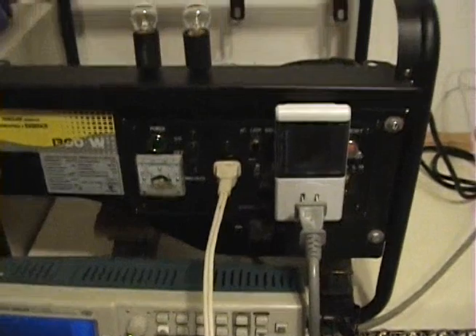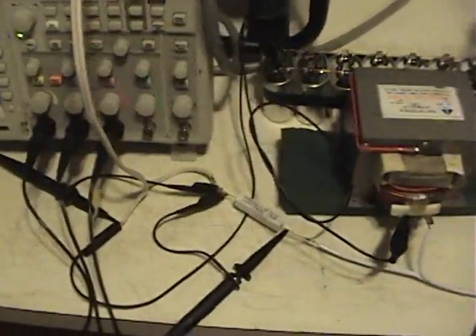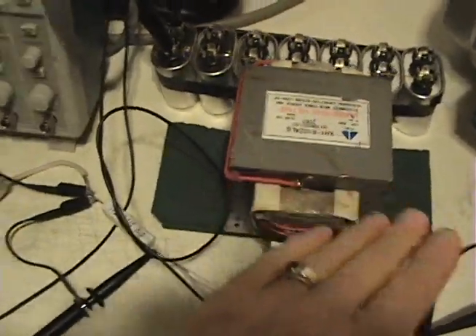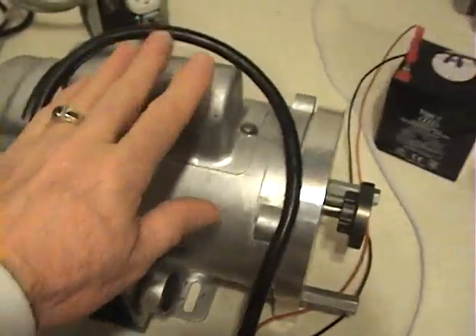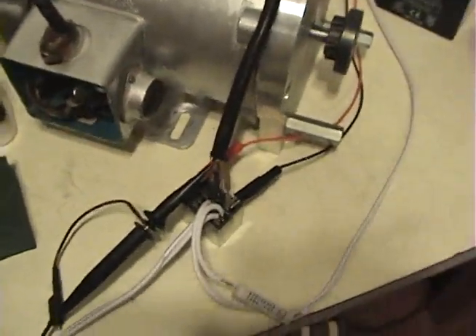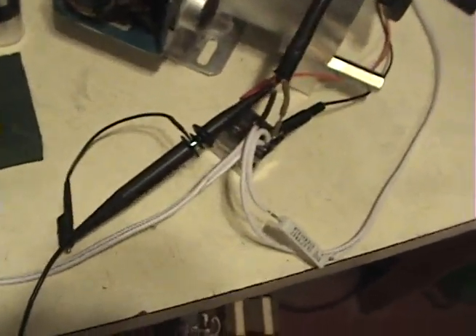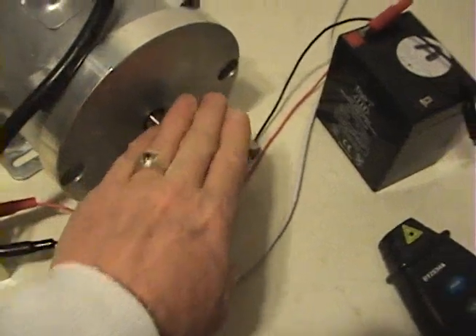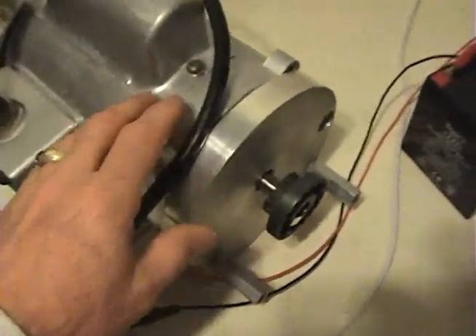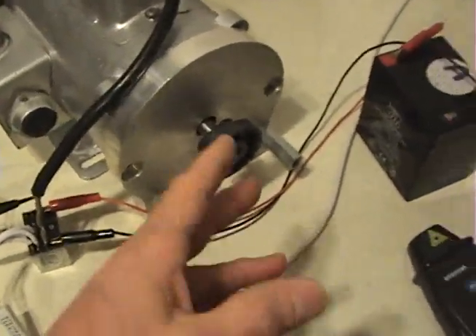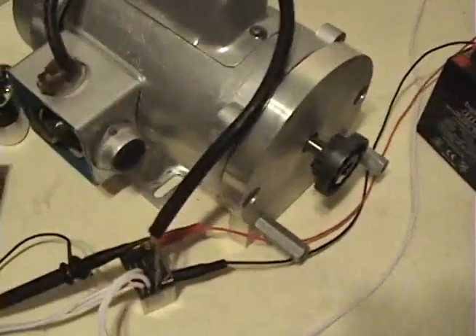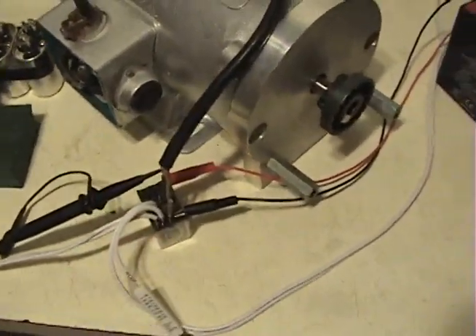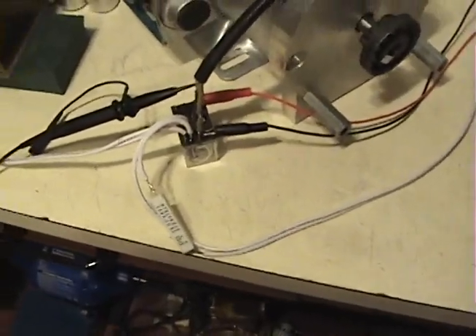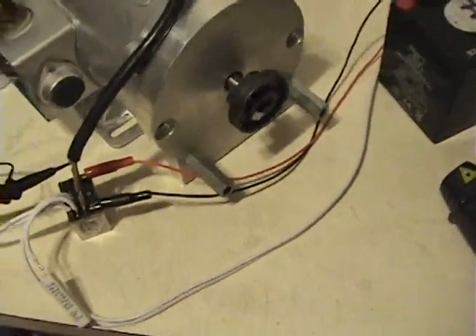Okay, we're back, and now instead of having a resistive load on the circuit, I've attached an induction motor to the circuit. I have to do a 120 volt grid start on the induction motor to get it going. If you remember on the other device, it also has to get going on the grid, but once the RPM is established, you can operate the induction motor on reactive power. That's what I'm going to demonstrate here, that this is also possible.